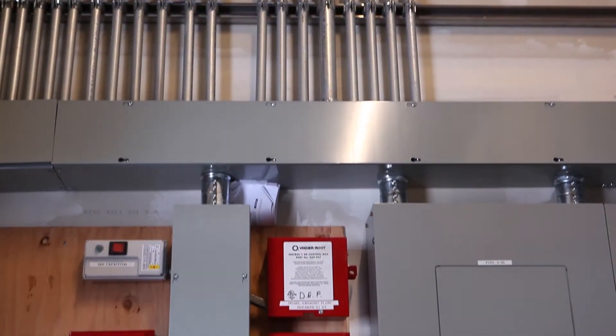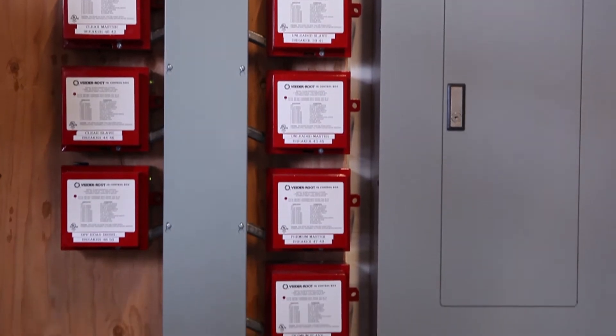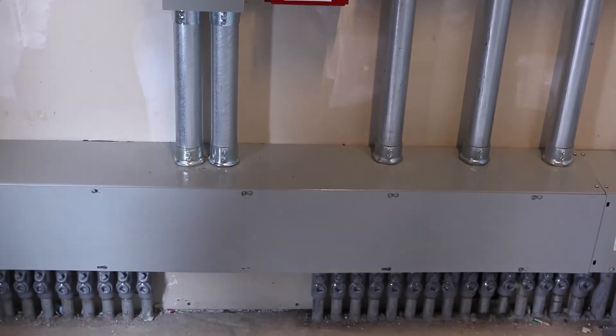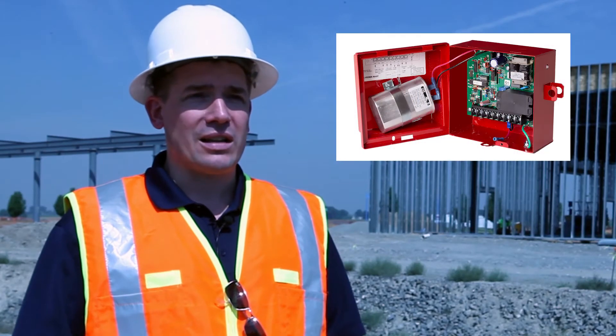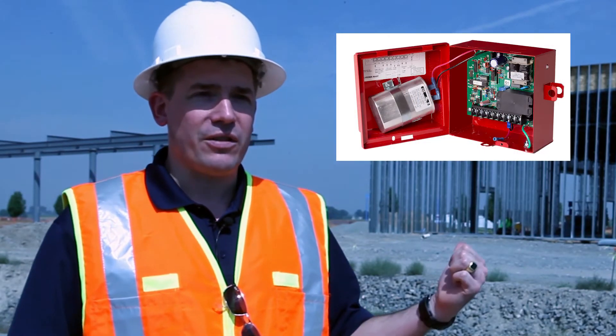Something we're very excited about from a Red Jacket perspective is that we've moved the capacitors out of the underground sump and put them back into the back room inside our controller box. That's going to give you longer capacitor life because it doesn't have the temperature and humidity fluctuations. Also, when it's cold outside and you've got snow on your tank lid and a bad capacitor, you can be drinking coffee in the back room getting it done and keeping the site up and running.